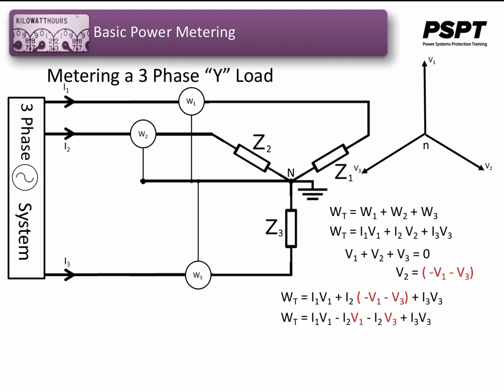Now we can collect like terms in this equation, and we see that the formula tells us that we only need 2 watt meters to meter this system. We collect like terms in terms of V1 and V3. We see that the total power consumption by that load can be metered with 2 meters, one using the voltage of V1 and the current I1 minus I2, and the voltage of V3 and the current of I3 minus I2. And the total would be the sum of those 2 watt meters, or 2 elements, that would be used to meter this Y-connected load.